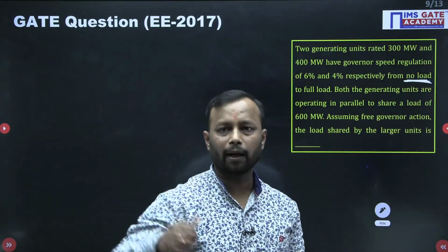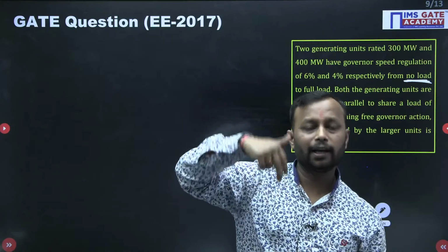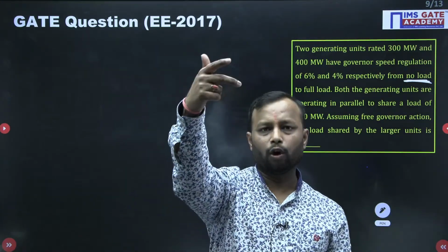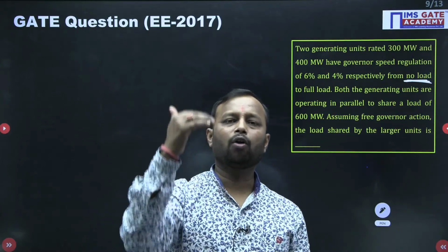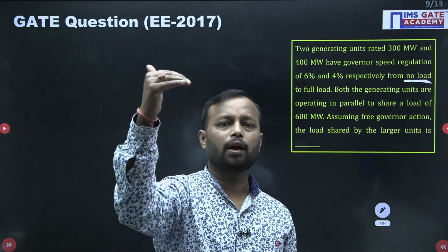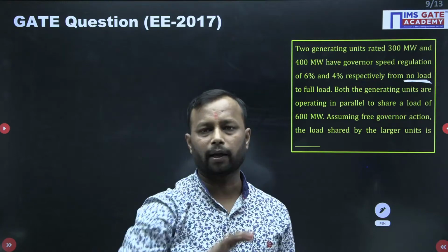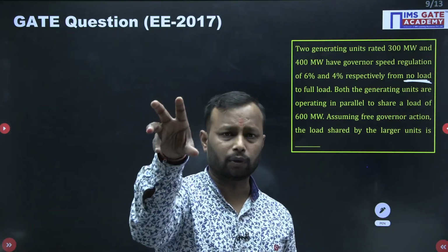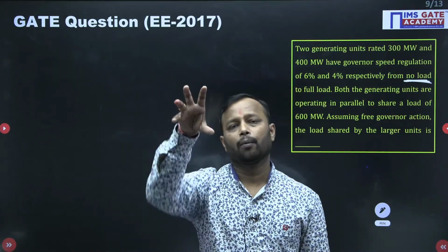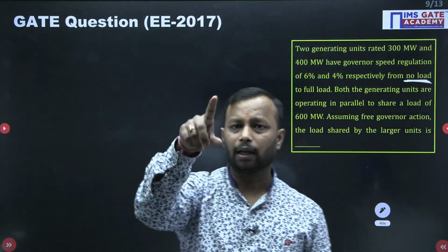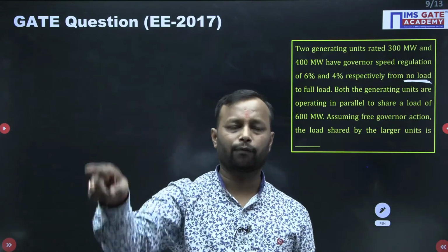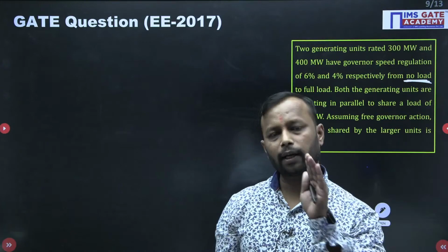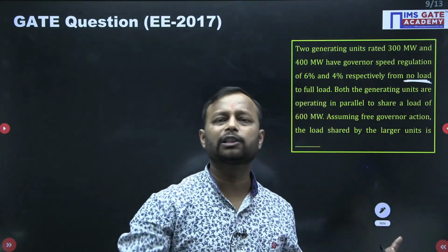देखो जैसे मैंने लास्ट केस लिया था ना, with the increment of the electrical power, the speed is going to decrease, but ideally the increment of the electrical power has to be coped with by the increment of the mechanical power. तो वो कैसे होगा? By injecting more steam over the turbine. If you inject more steam over the turbine, then the turbine is going to rotate at a faster speed, therefore the frequency is going to increase. तो ये किसका काम है? गवर्नर का, जिसको बोलते हैं स्पीड गवर्नर.